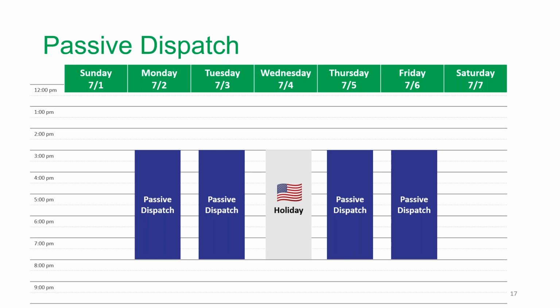In this example, in July your battery would discharge over 5 hours from 3 to 8 p.m. on all non-holiday weekdays, except for the 4th of July, where it would not dispatch because it's a holiday. And of course it doesn't do that on weekends either. So your battery will be discharged, leaving about 20% capacity on all of these days.